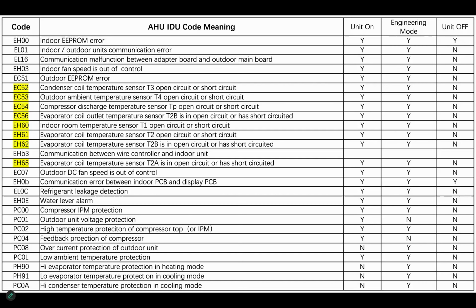So the actual range isn't important right now. The only thing I'm looking for is to see that all three are the same, or they're within that 1/10 ohm deviance. Okay, so where it's at doesn't matter. I want to see if they're in range of one another. If that checks okay, check them to ground. Make sure you don't have any resistance to ground on them. If that checks okay, we're going to start looking at the inverter.